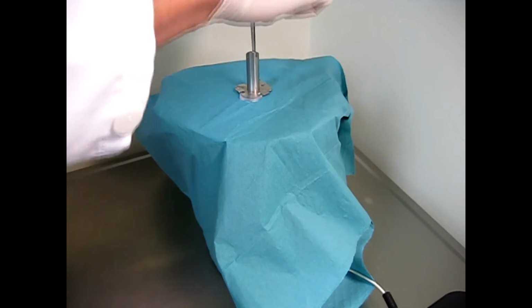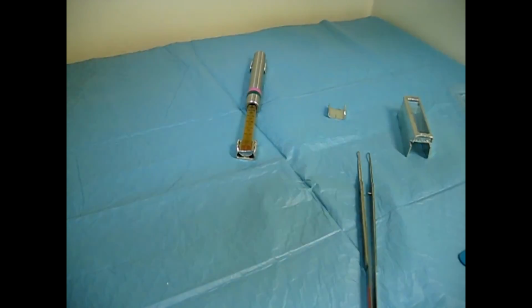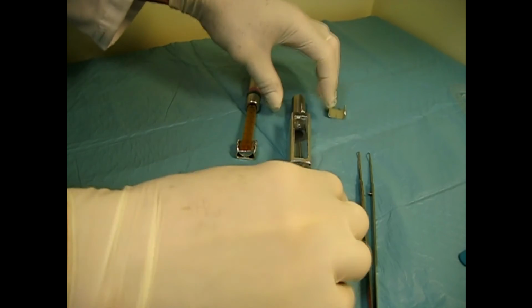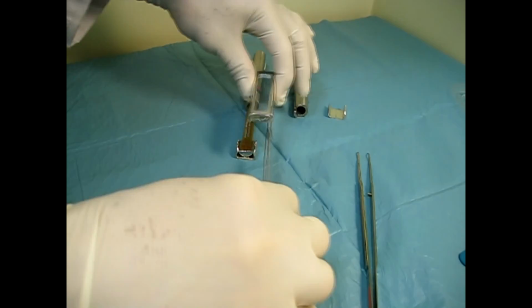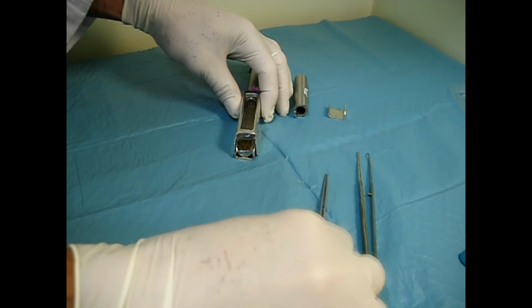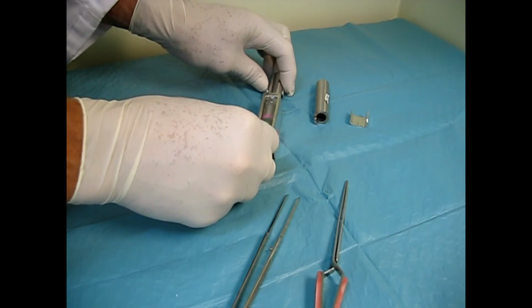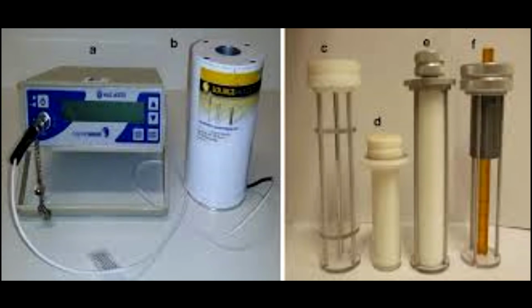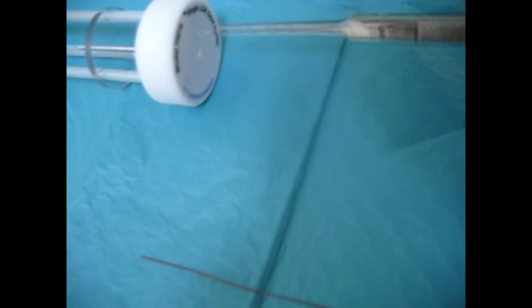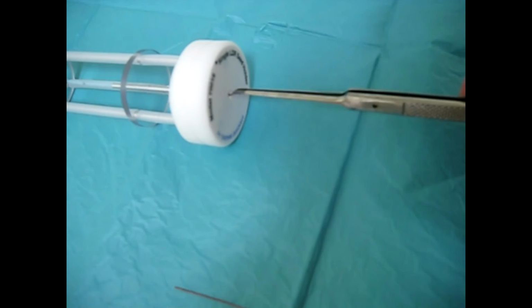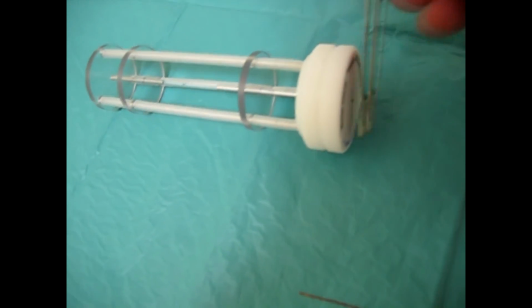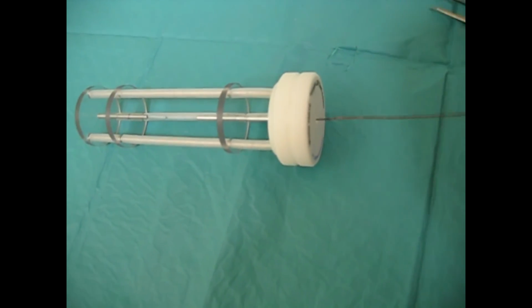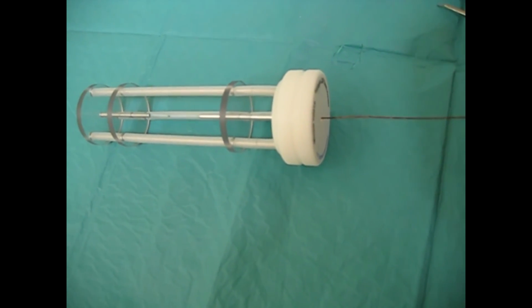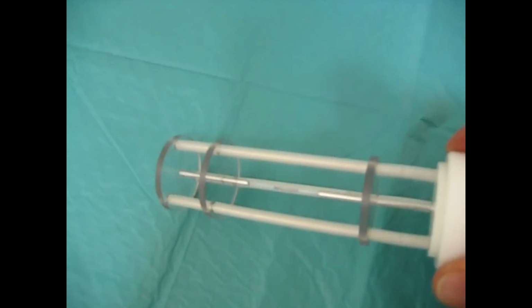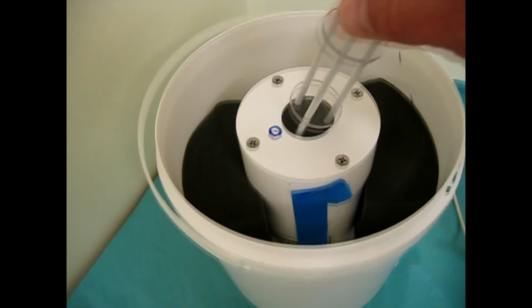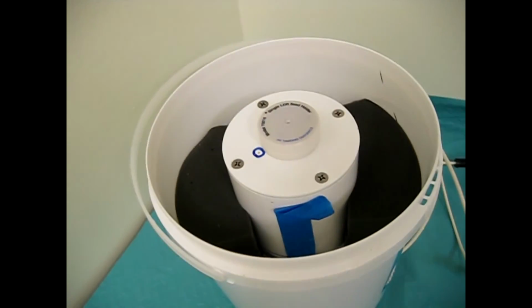For the returning strands back to the plastic jig, we do all steps in the reversed order. Remove strand from short cylindrical transport container and position strand on jig. To find calibration factor for well chamber, when we use 4 or 5 or 6 seeds in strand, we need to measure activity of every single seed enclosed in the strand by standard procedure using single seeds iodine 125 calibration factor from standard imaging.